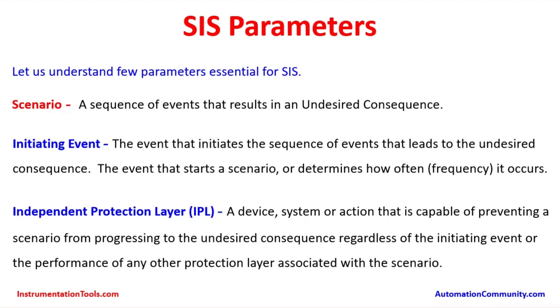The first parameter is Scenario. A scenario is a sequence of events that results in an undesired consequence. As seen in LOPA examples, LOPA sheets cover different parts of the plant and there could be multiple hazard scenarios. One example is a boiler with fuel gas — it may go to high pressure due to failure of a control valve. This is one particular scenario.